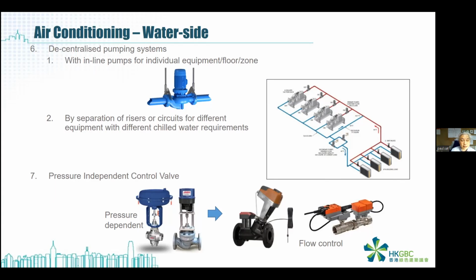And the seventh one is we also use the pressure independent control valve. In conventional systems, most of the control valves are pressure dependent. We use the temperature to control the valve opening. If you meet the set point, then the valve will be closed. If you cannot meet the set point, the valve will be open for cooling, something like that.